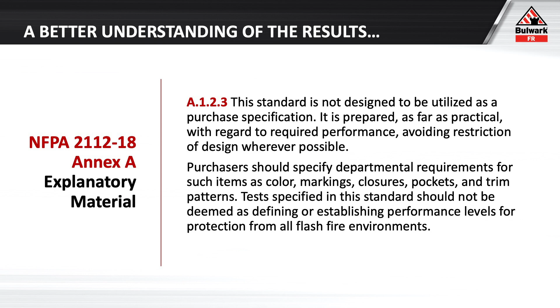Why is that important? It's important to understand the difference between a laboratory, where I have my 8 burners, I have my 360 degrees exposure, I have my full 3 seconds of exposure, then I collect data for 60 seconds on the mannequin. Versus a real world rapid moving flame front, which is the flash fire hazard on our facilities. So you'll notice here we have a facility, we have propane, and we have an ignition source that we have highlighted. Within the 22/100ths of a second of touching that ignition source, you can already see the flame front is starting to advance back to the source.